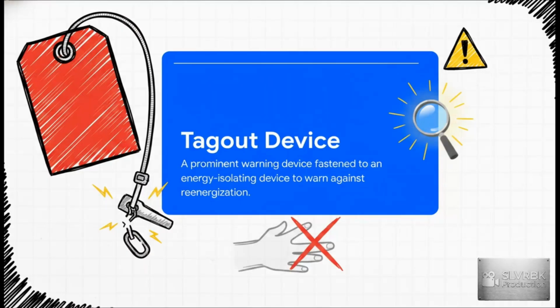Now, a tagout device, on the other hand, is essentially a prominent warning mechanism. It provides absolutely zero physical restraint. Because it relies purely on warning people not to re-energize the machine, OSHA has incredibly strict rules if you're going to use one. A tag has to be fastened with a non-reusable, self-locking nylon cable tie, basically a really beefy zip tie that requires a minimum unlocking strength of 50 pounds. It's meant to be tough to break, for sure, but remember, it can still evoke a false sense of security compared to a physical lock.